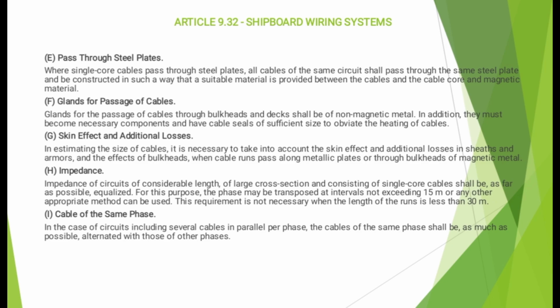Pass-through steel plates. Where single-core cables pass through steel plates, all cables of the same circuit shall pass through the same steel plate and be constructed in such a way that a suitable material is provided between the cables and the cable core and magnetic material. Glands for passage of cables. Glands for the passage of cables through bulkheads and decks shall be of non-magnetic metal. In addition, they must become necessary components and have cable seals of sufficient size to obviate the heating of cable. Skin effect and additional losses.